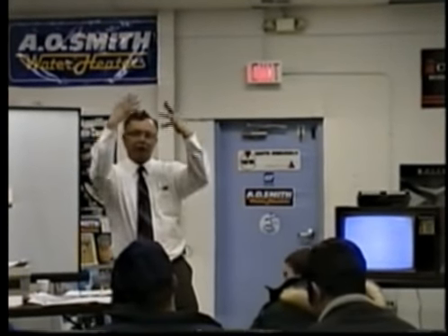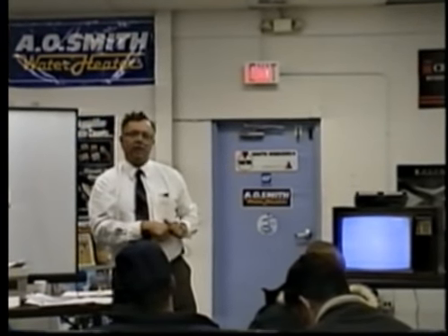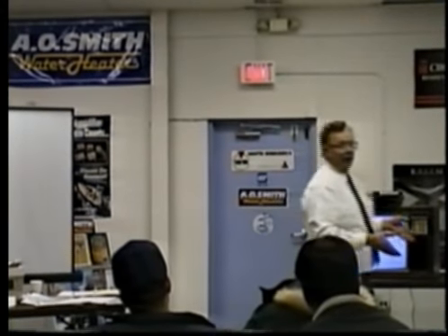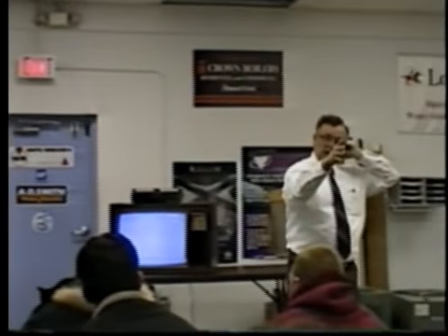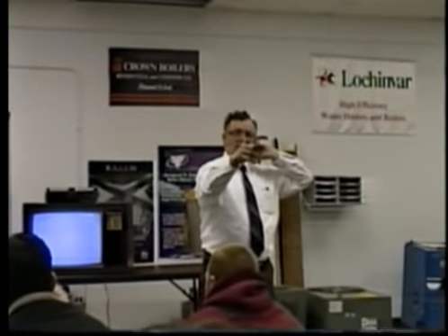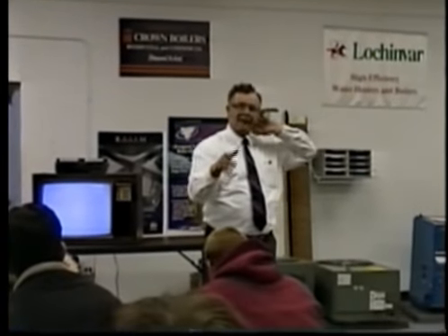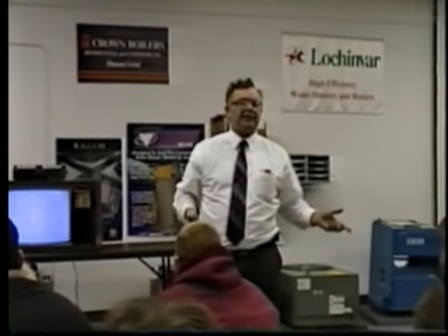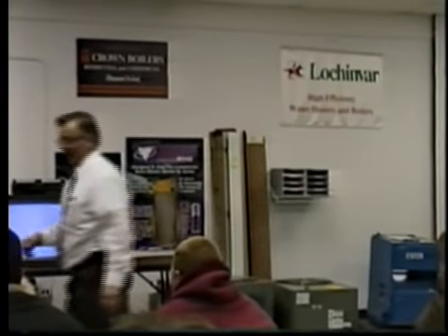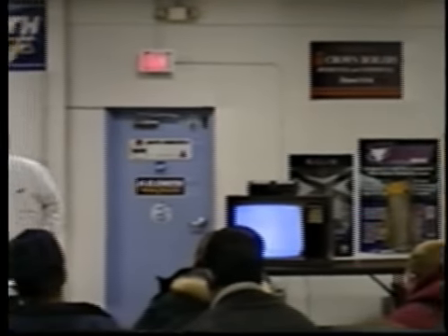You see what I'm saying? So if it cools off, it cannot dehumidify then. But while it's running, it's still dehumidifying, and that is a very common problem. The customer doesn't complain that it's not cool enough. They complain that it's too cold and clammy in the house. See? Okay? Questions?